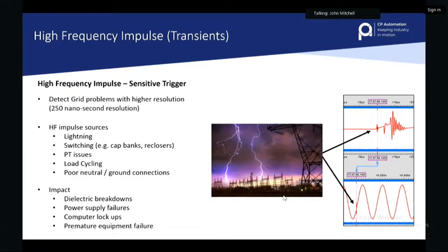Those are really fast spikes though - these aren't sustained over-voltages. Most people only think of transients coming from lightning, but the reality is 80% of transients are created within your own factory or your customer's factory by their own equipment. That can be switching over between generator and mains, fast acting direct-online switching, big chillers coming on and off. There are so many other things that can cause transients within the network.